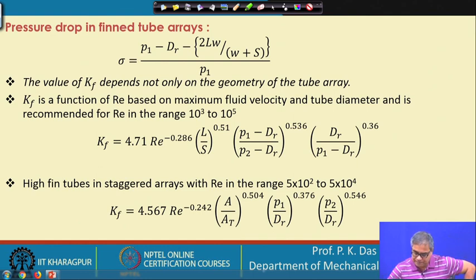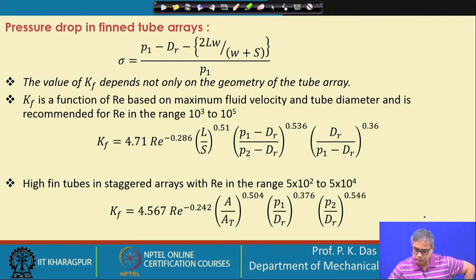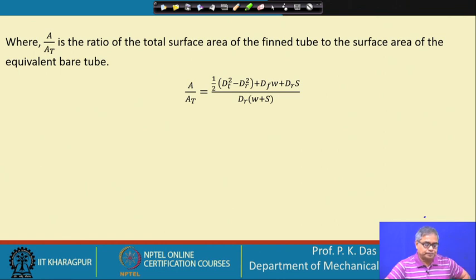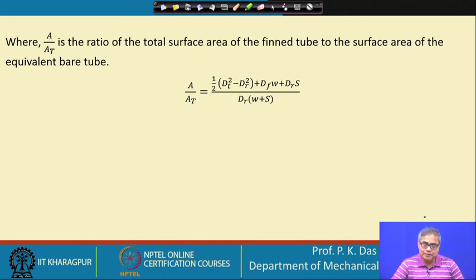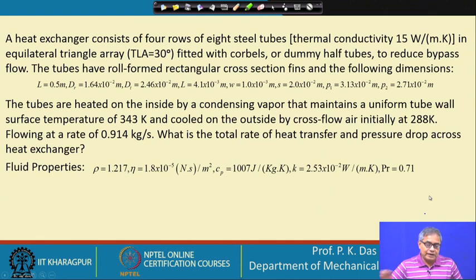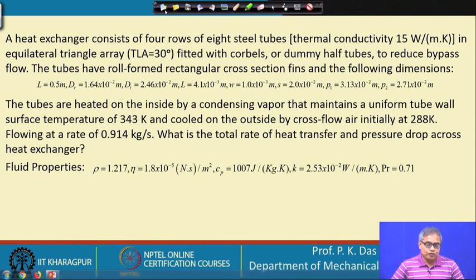Delta_P depends on K_a and K_f. K_a depends on sigma, and the slide shows how to calculate sigma along with existing correlations for K_f. Now let us move to the next slide. The ratio A/A_t is the ratio of the total surface area of the fin tube to the surface area of the equivalent bare tube. With this we can calculate the required quantities. Let us take up a problem to see how we can use what we have learned.